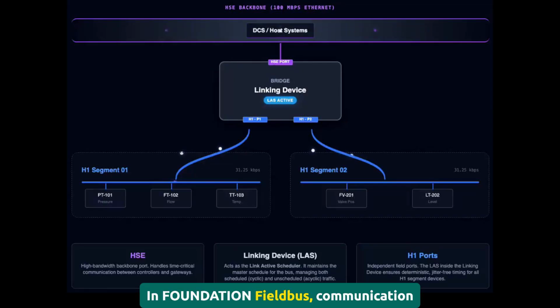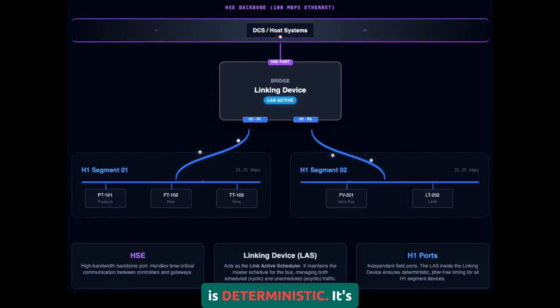In Foundation Fieldbus, communication is deterministic. It's scheduled. Every device gets a turn to talk. The LAS makes sure there's no collision and no stepping on each other. Device 1 sends for 20 milliseconds, then device 2, then device 3. It all happens in a specific order every cycle, like clockwork. That's huge for control applications where timing matters. And in industrial control systems, timing always matters.